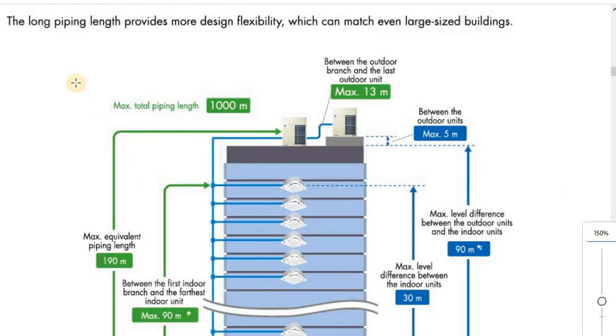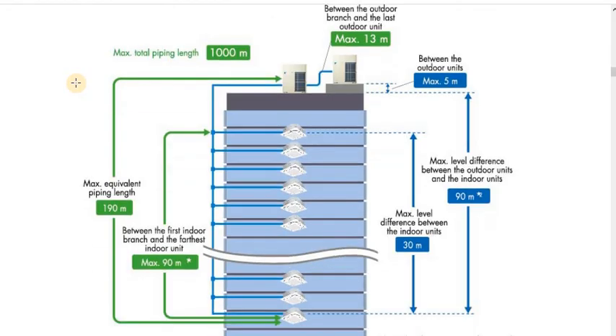This is the pipe length and height limitation of the Daikin VRV system. The first one is the 1000-meter piping length, the maximum total piping length. What does this mean? This means you can use up to 500 meters in suction and 500 meters in discharge. Okay friends, this is the first limitation.